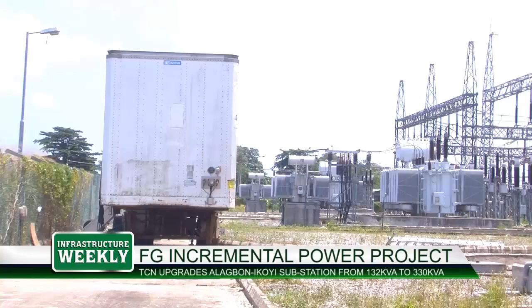Like this one now, you can see the pipes are connected. So the essence of bringing this plant is to renew the oil in that transformer, to bring it back as if it's new oil, because after operation the oil starts degrading. So the essence of this machine is to bring the oil back to normal operational efficiency.